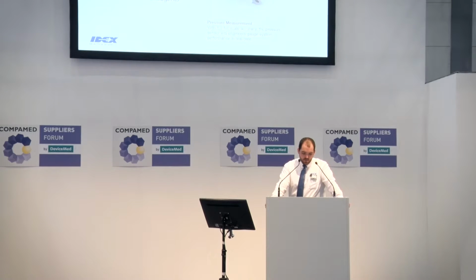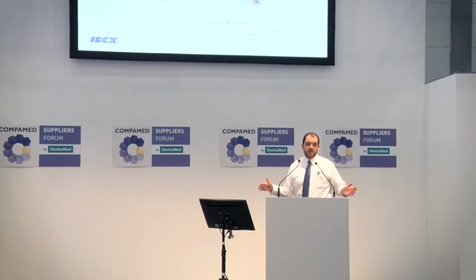We have 1% full-scale accuracy, and our scale is for 14 bars. So in other words, you get around 200 PSI, and this is 14 bar absolute. So that means these pressure sensors also measure in vacuum down to 0.25 bar absolute. And you have 1% accuracy across that full scale. So that's pretty good. Like we were talking about earlier, it has a flow-through design. That was really important to a lot of customers. So the flow-through design prevents bubbles from getting trapped in there. It prevents excessive carryover.